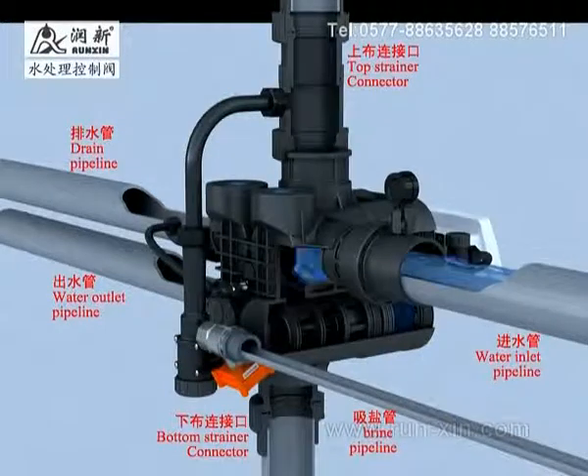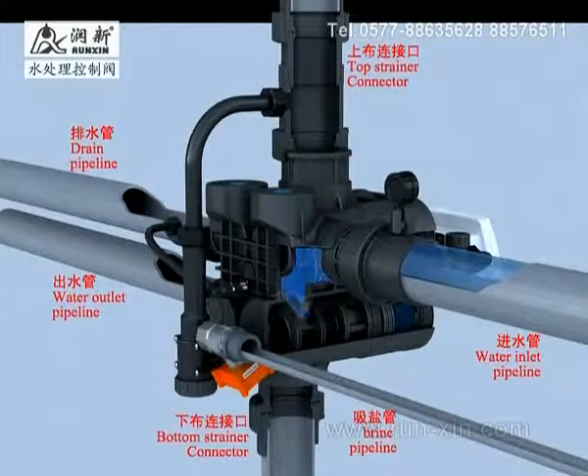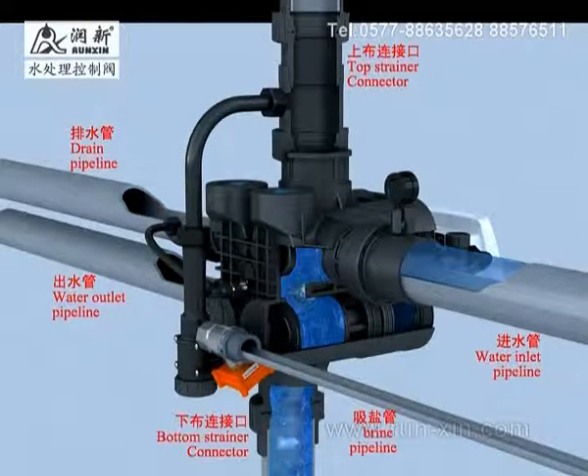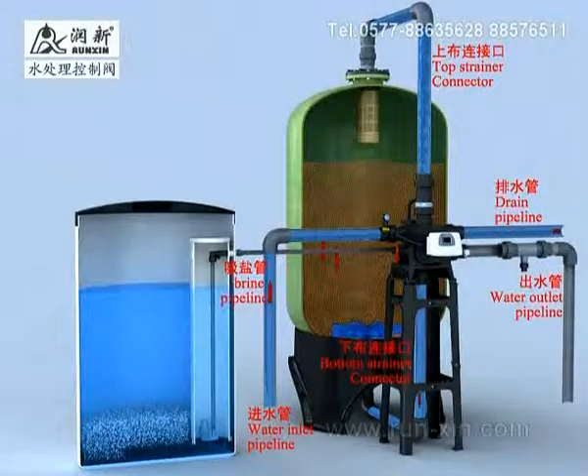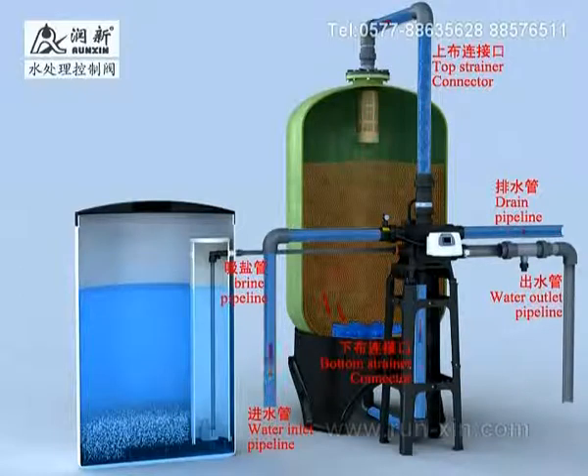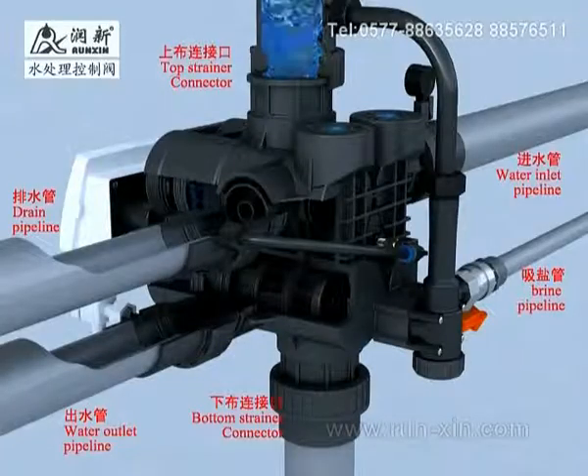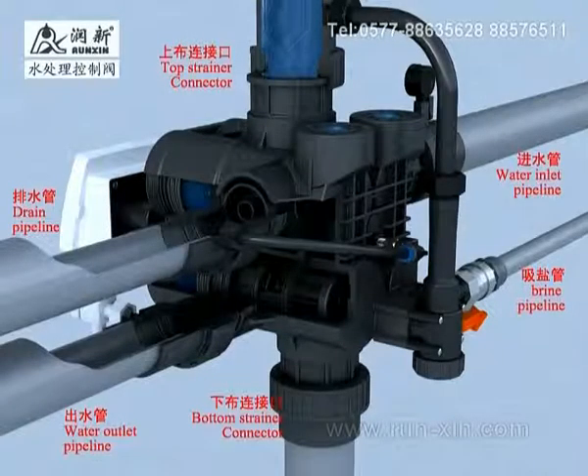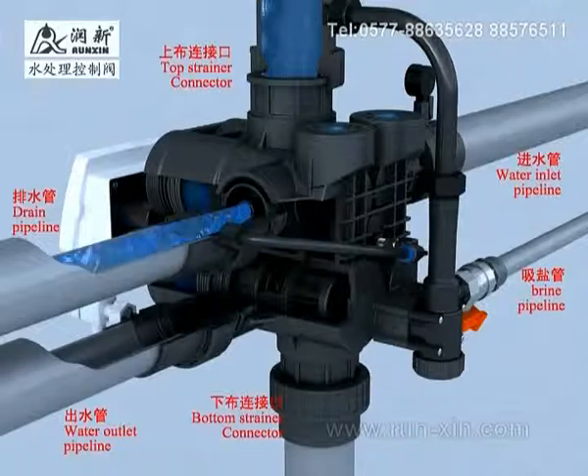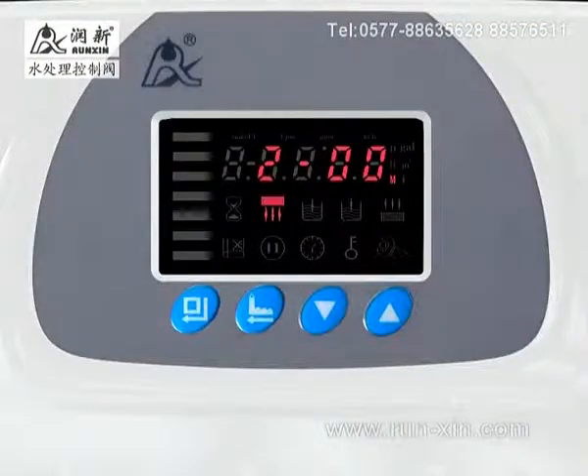Raw water through the inlet goes into 3 port valve A and B, then through the bottom strainer to the tank. Under the influence of water flow, the resin layers are loosened. The broken resin and dirt return to 3 port valves, and finally flow out from the drain outlet. When backwash time reduces to 0, it is over.